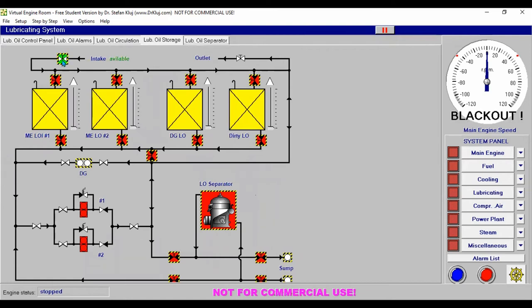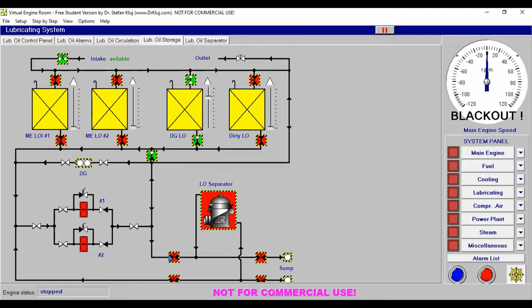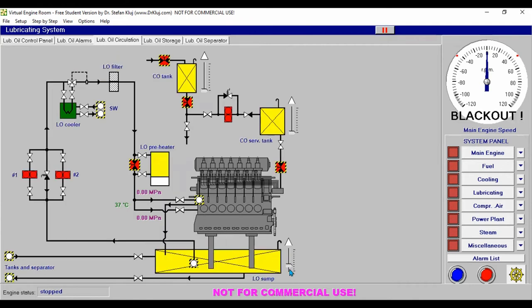In our lubricating system, at our LO storage, we need to fill our DG lube oil storage — coming from the diesel intake going to the diesel lube oil storage supply. You can see the level rising. It lines up going to the sump of diesel generator number one, and now it's filling up. Close the valve and trace the line going to the sump.